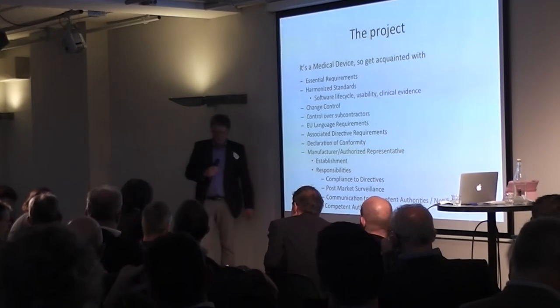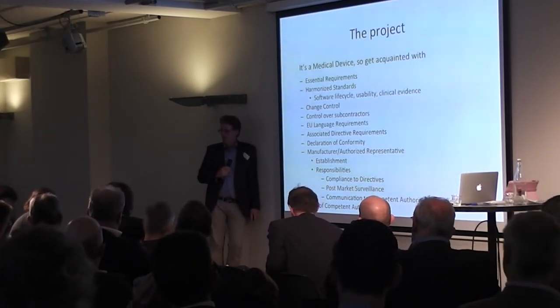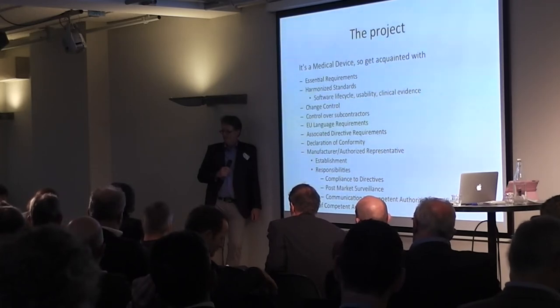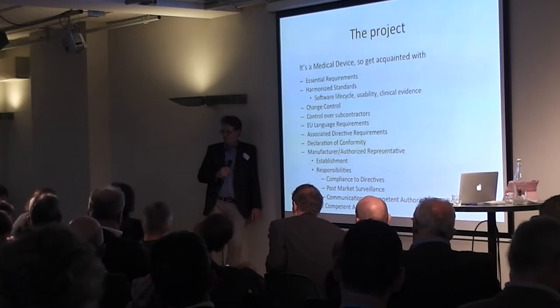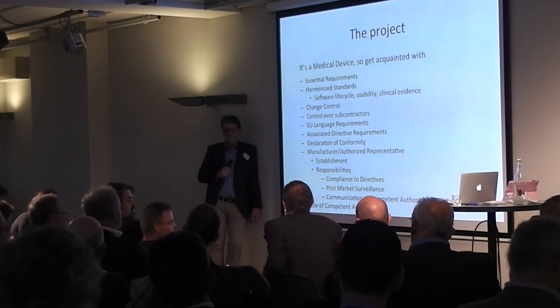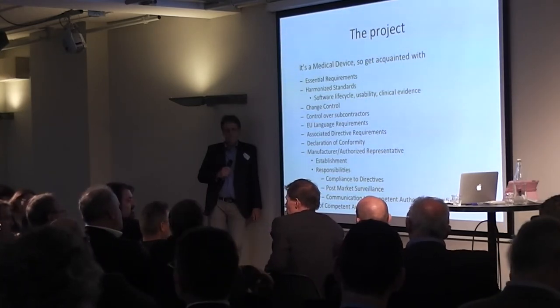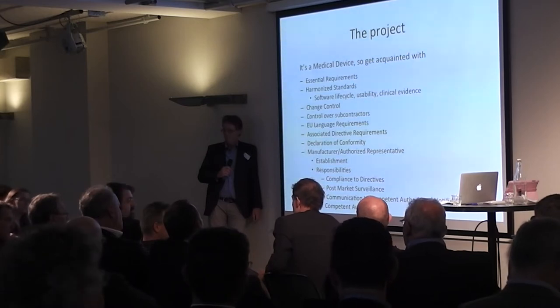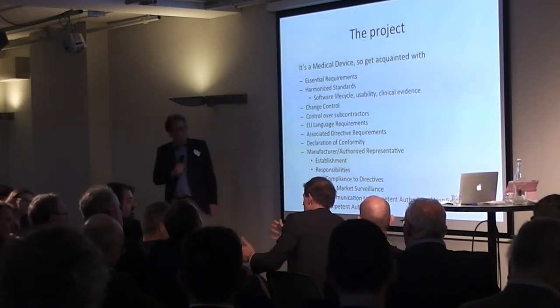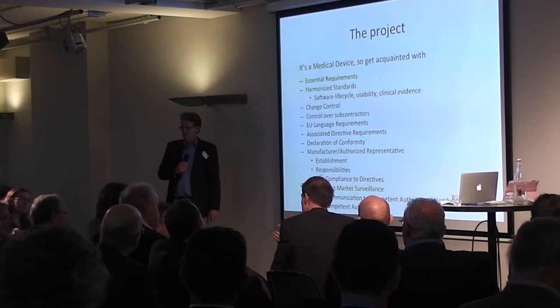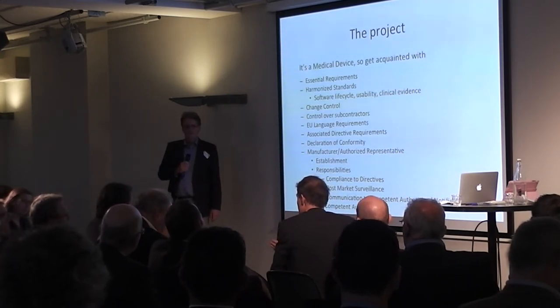Does that mean that you can refer to existing evidence from traditional medical literature stating that the size of the melanoma is indicative for the prognosis? Or does it have to be a software-specific reference? That's a good question — what you need to do is develop a process of clinical evaluation, which means you start to look for relevant sources. Then based on these relevant sources, you say: this is what I can substantiate, this is what my product intends to do. Does that overlap? If there is a gap, then I might need to do a clinical trial to close that gap.